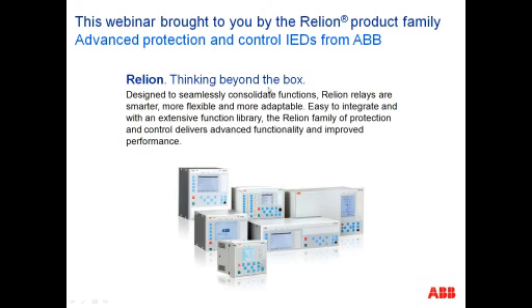So it's certainly the protocol of the future. The 61850 standard itself allows interoperability between multi-vendor products. A good example would be the TVA Bradley 500 kV Bradley substation, which is a 61850 substation between ABB, Siemens, and GE.